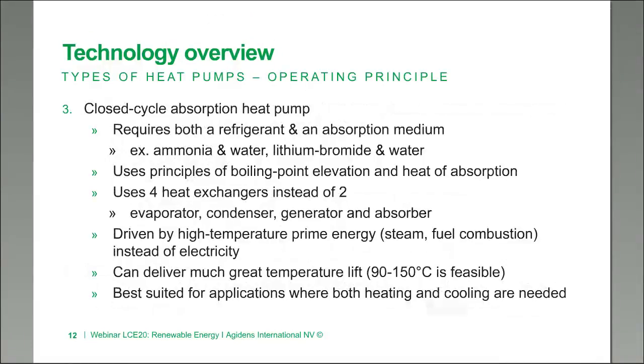The third type is the closed cycle absorption heat pump. In an absorption heat pump you use not only a refrigerant but also an absorption medium — for instance ammonia and water, or lithium bromide and water. These are two common types of medium used. The closed cycle absorption heat pump uses the principle of boiling point elevation and heat absorption, and uses four heat exchangers instead of two: an evaporator, a condenser, a generator, and an absorber. These systems are driven by high-temperature prime energy, which could be steam or fuel combustion — thermal energy rather than electric energy.